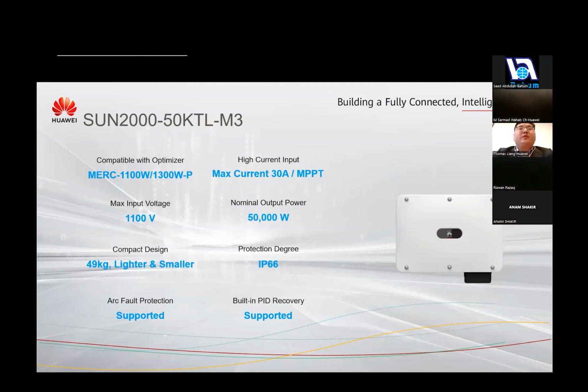Another new product for the commercial and industrial scenarios is the 50 kTL M3. It will be compatible with our new generation optimizer, which I will introduce in the following slides. And the same as our new product, the maximum input current of each MPPT will reach 30 amps, so that means you can be compatible with high current modules. And the size and the weight will be lighter and smaller compared with the last generation 50 kTL and the 60 kTL M0, so it's easier for installers to handle on site.